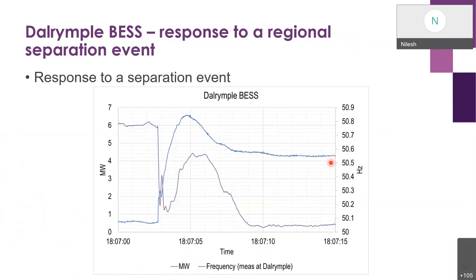The next one is the response to a separation event. We had one incident when the whole South Australian region was separated from the rest of the region, and this is the response from the battery during that event. When the separation occurred, the region was exporting. That's why you see the frequency going up, and the battery started to absorb megawatts. You can see an inertial response, which you'd likely see from a synchronous machine during the first second or two. After that, the response was largely governed by the frequency control ancillary service market requirement, which we call FCAS in Australia. So it's a combination of inertial response and frequency response shown on this slide.